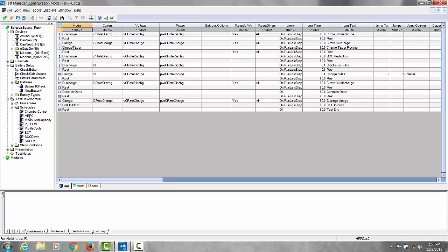We've now completely configured communications, the battery pack, and the test schedule, all through spreadsheets that we found just by walking through this directory structure, and in a way that will ensure consistency and save time for all of our future testing using the BTS Test Manager. Let's take a quick look at the other iTest interface, the Operators Console.